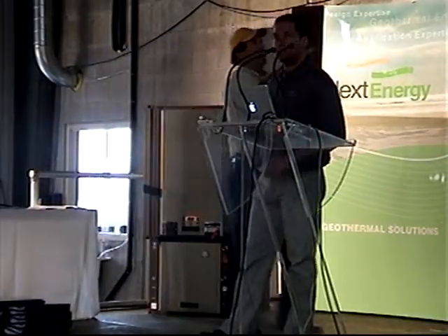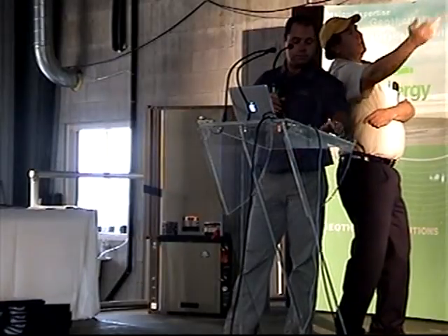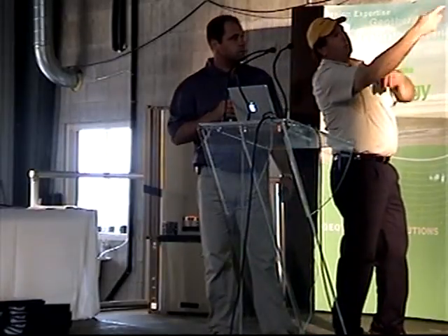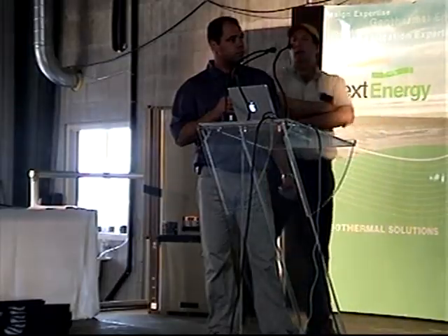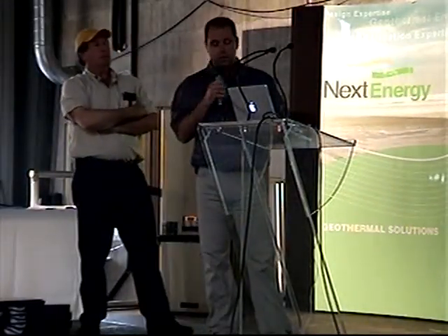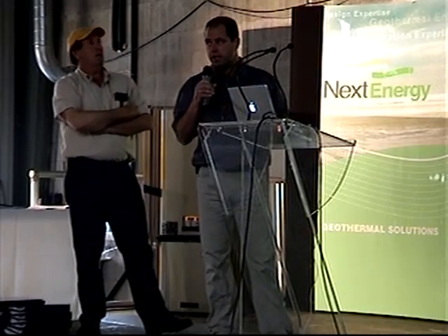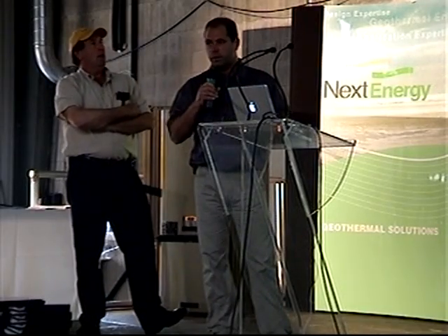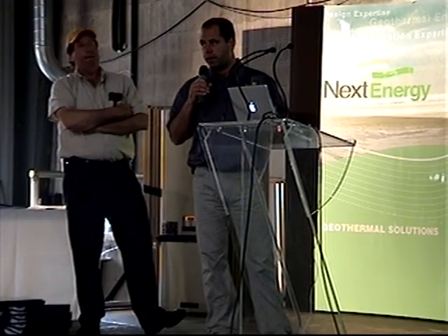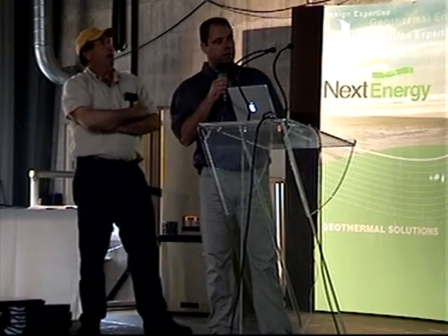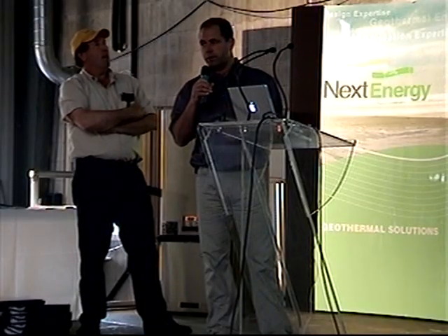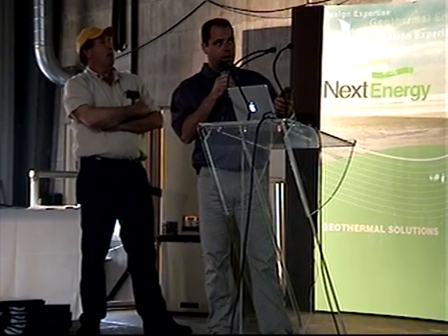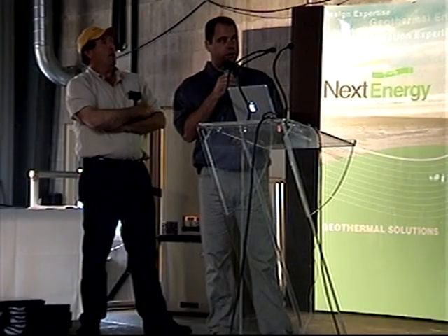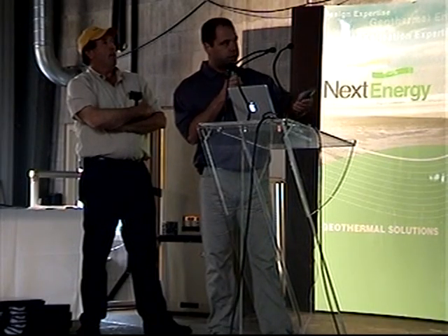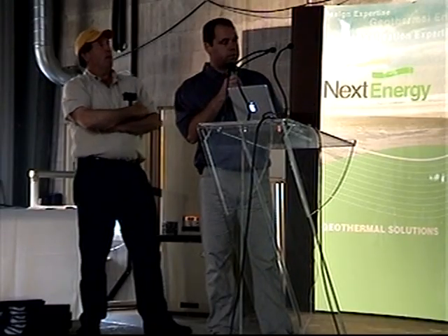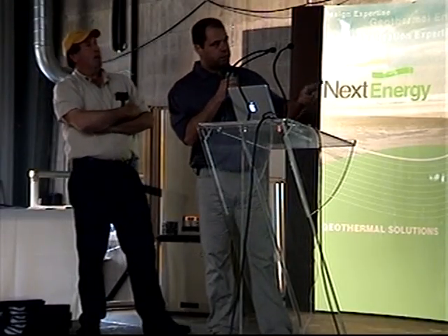These could change as we reverse it, eh? One's your coax, the other's your evaporator, and they change back and forth depending on what we're doing, eh? Right, well, I'm sure you know the evaporator is what removes heat either out of the water coming from the loop or removes heat from the air inside the house. And the condenser is what rejects heat either into the water from your loop or through the air coil, putting the heat into your house. So it's all about transferring heat from the ground to the house or from the house back to the ground. And this is the cycle that makes that happen.